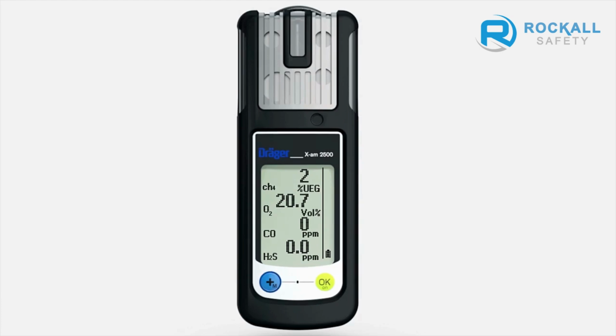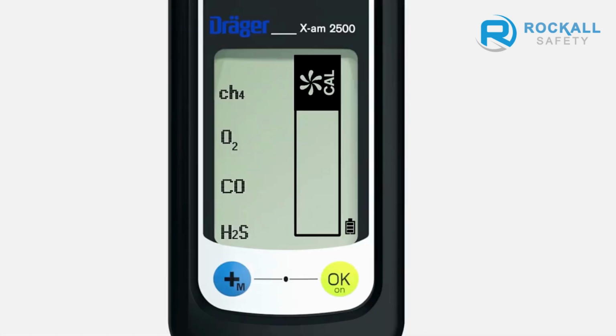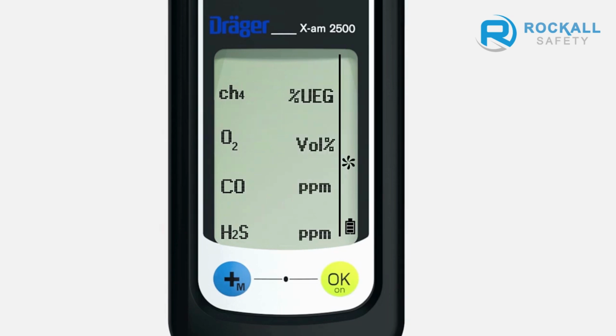Press the plus key briefly 3 times. This symbol appears. Press the OK key to activate fresh air calibration. The flashing numbers show the actual values.